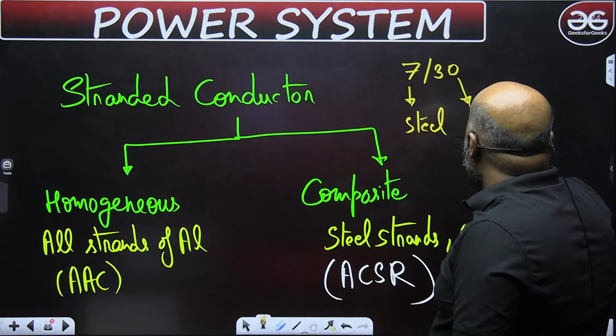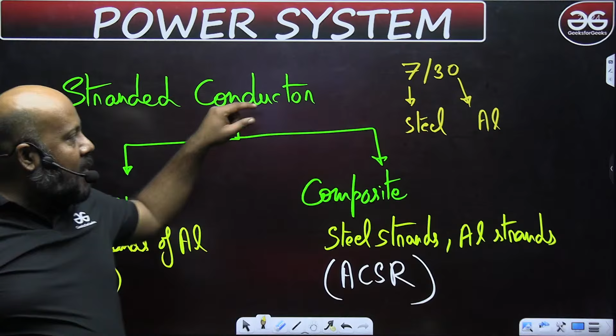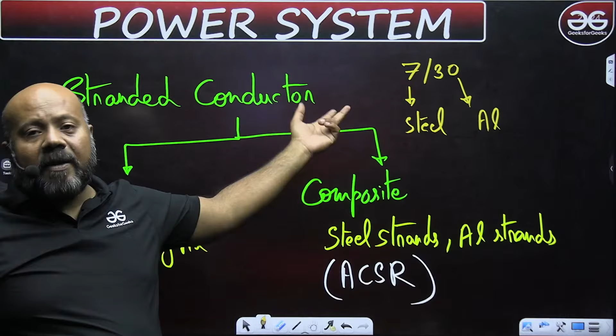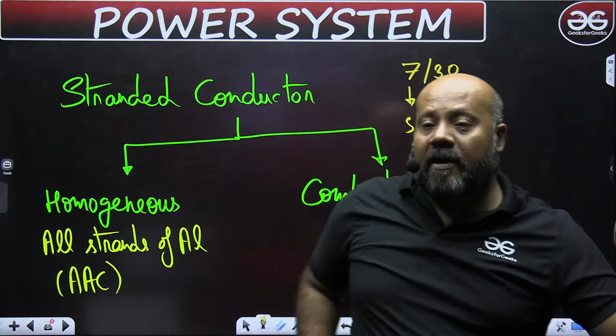For composite conductors, always remember, if it is written like 7/30, the smaller number of strands will belong to steel, because steel is not going to carry the current. Only the aluminum strands carry the current. This is how we represent ACSR conductors: number of steel strands and number of aluminum strands, or vice versa. Always the lesser number of strands belongs to steel.